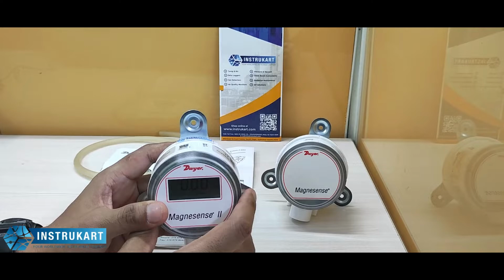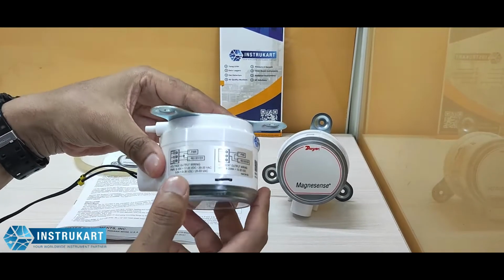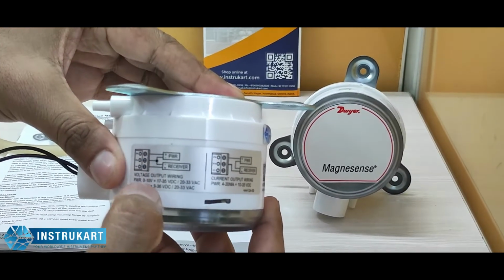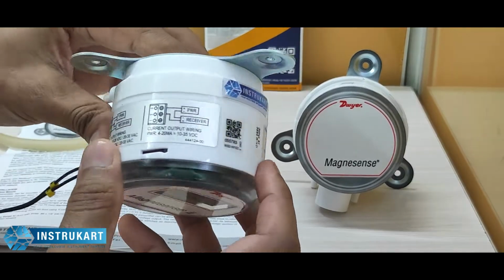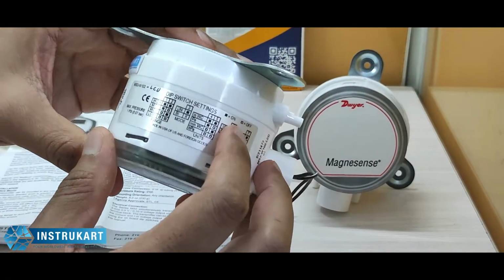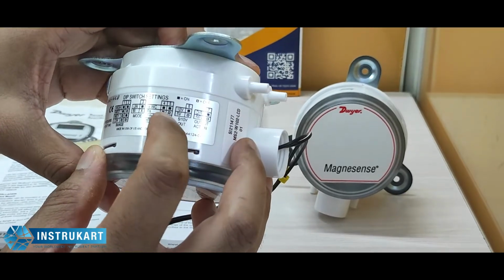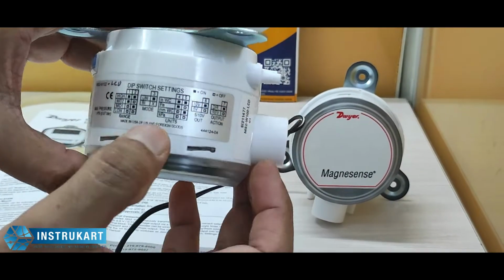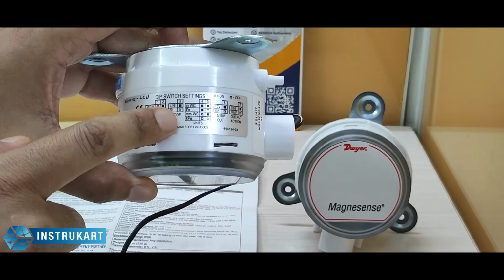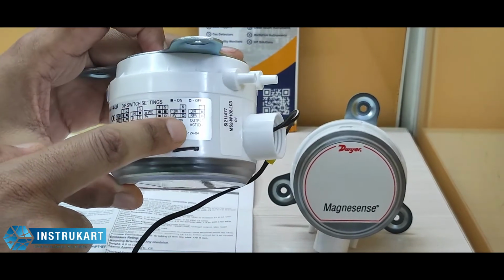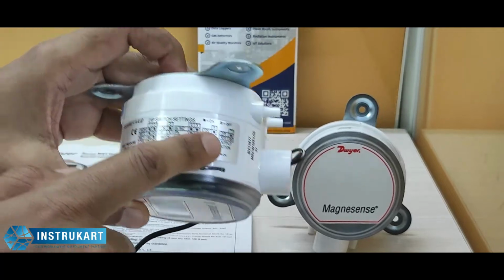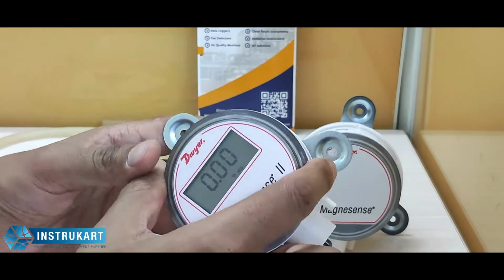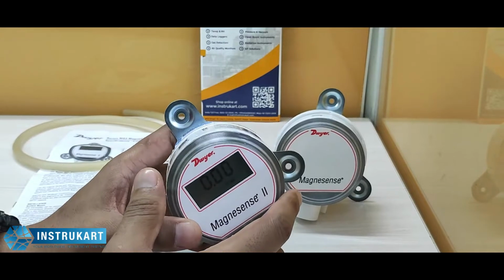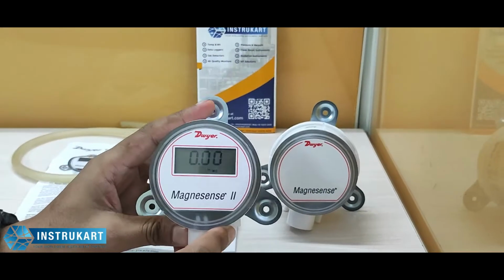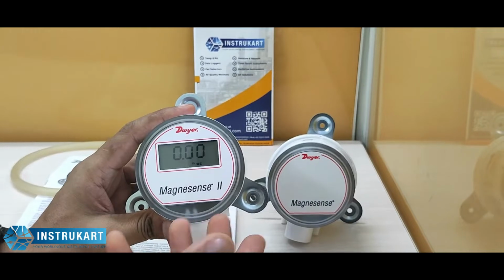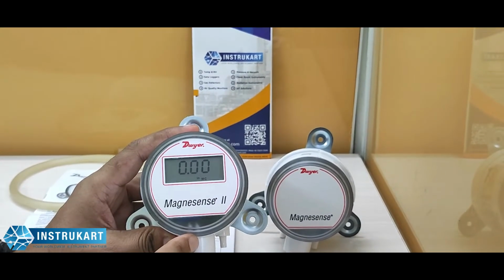Now in this instrument you have different settings which can be done basically between the VDC, DC and AC power. You also have the dip switches for toggling between inches water column, Pascal, MMWC and kilopascal. You also have the output option which can be set. The power requirement is 10 to 35 VDC 2 wire, and it has an output signal of 4 to 20 milliamps, which means that you can connect to your PLC or SCADA system where you can acquire the data.